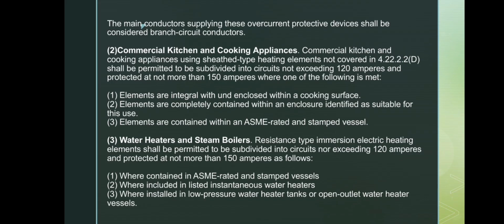Next, the main conductors that supply the overcurrent protective devices are treated as branch circuit conductors. For commercial kitchen and cooking appliances, their sheathed heating elements may be divided into circuits up to 120 amperes with protection not more than 150 amperes, if any of the following is true: the elements are built into and enclosed within the cooking surface, they are fully enclosed in a housing approved for this use, or they are inside an ASME rated and stamped vessel.